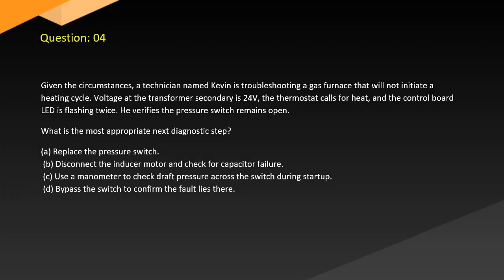Question 4. Given the circumstances, a technician named Kevin is troubleshooting a gas furnace that will not initiate a heating cycle. Voltage at the transformer secondary is 24. The thermostat calls for heat, and the control board LED is flashing twice. He verifies the pressure switch remains open. What is the most appropriate next diagnostic step? A. Replace the pressure switch. B. Disconnect the inducer motor and check for capacitor failure. C. Use a manometer to check draft pressure across the switch during startup. D. Bypass the switch to confirm the fault lies there.